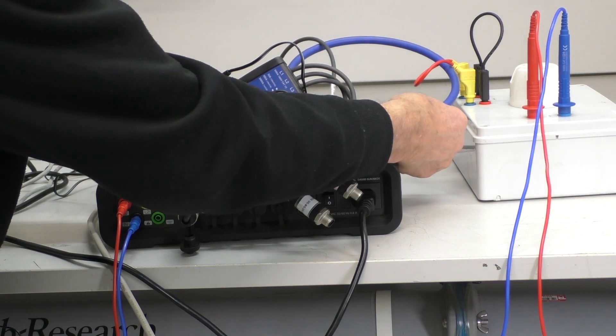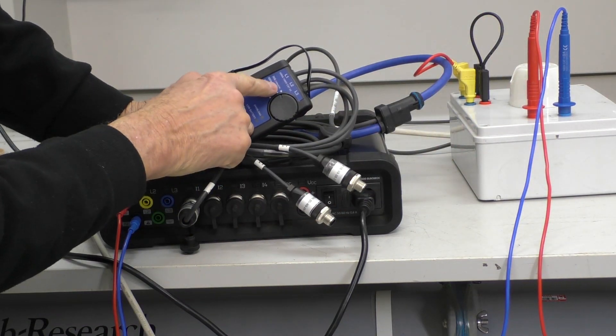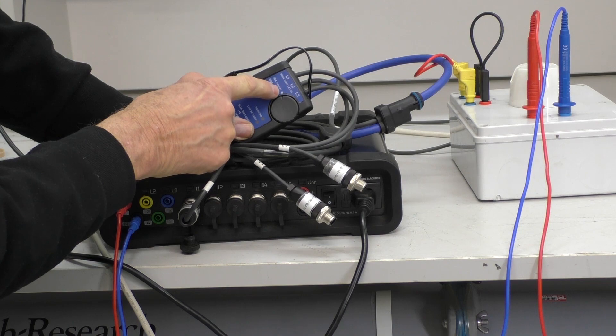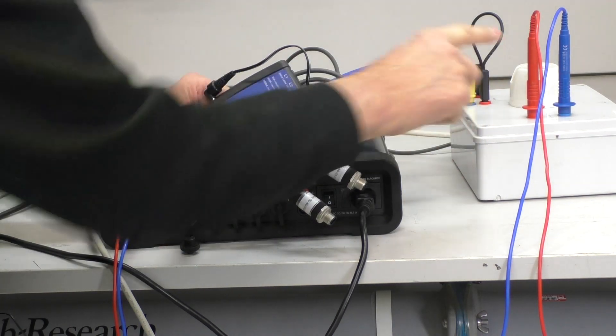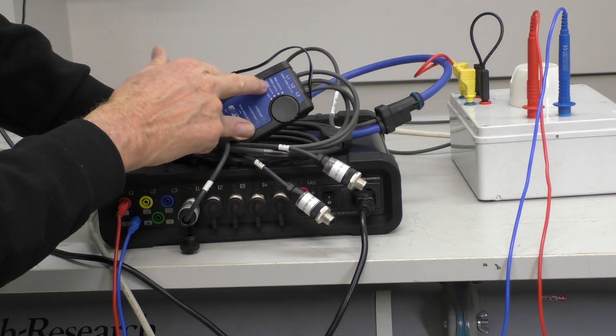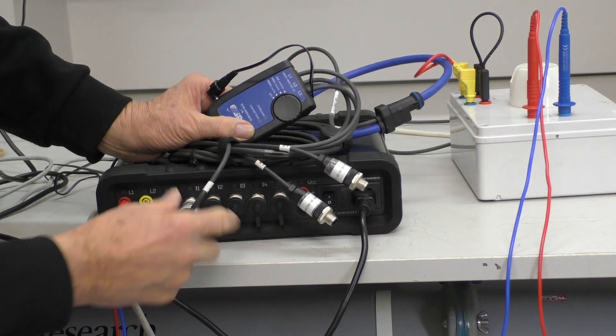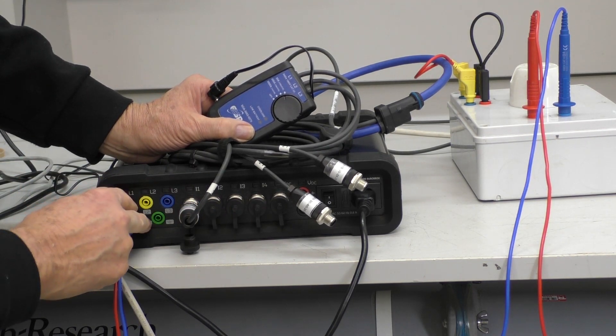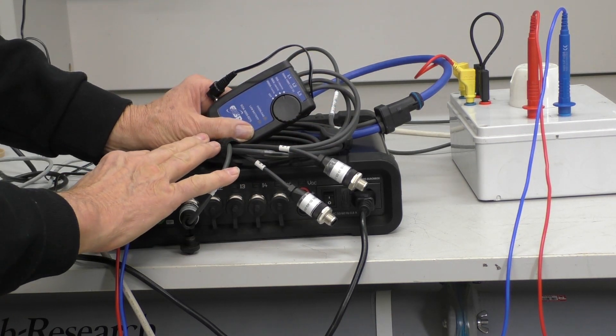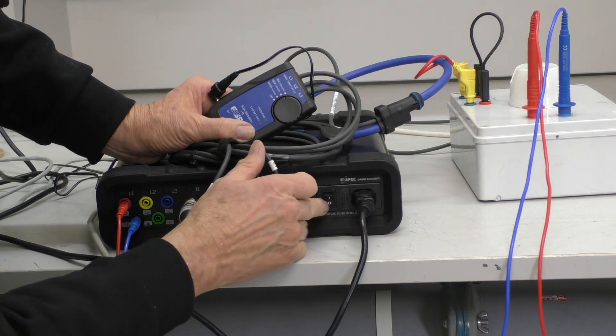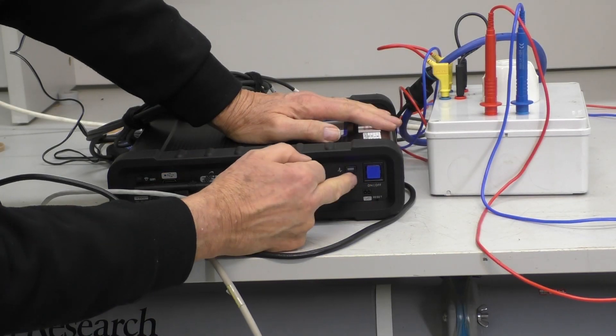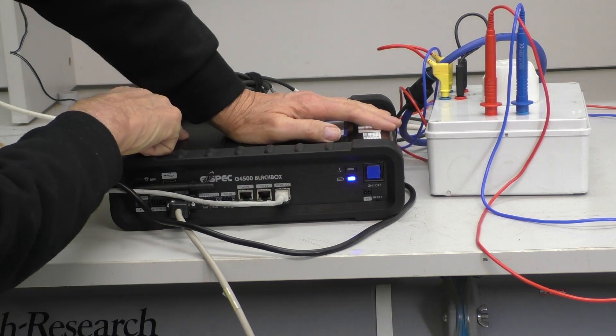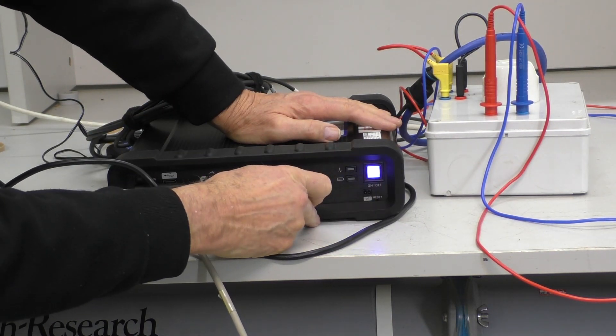Okay, I've connected the flexible clamp up here so I'm measuring the current. I've set the range to 100 millivolts per amp range, a 30 amp range because we're not going to draw too much current out of this single phase. We can go up to 3000 amp range if we need to. And I've connected it up, I've got voltage connections so this is ready to run from a connection point of view. I'm also going to turn the instrument on. Okay, the instrument has two on switches. There's one on the back and now there's one on the front so I'm going to switch it on from here.